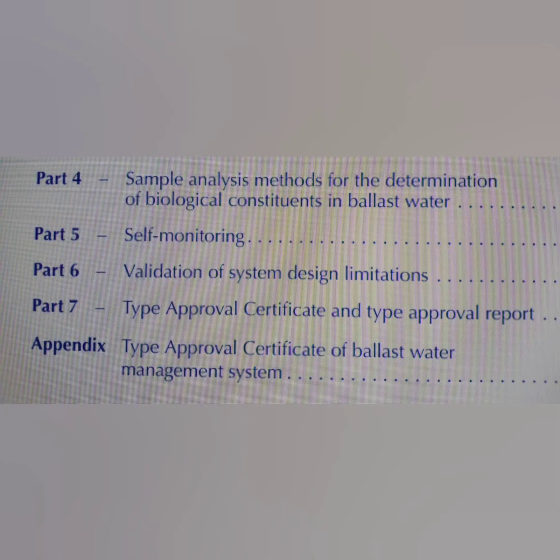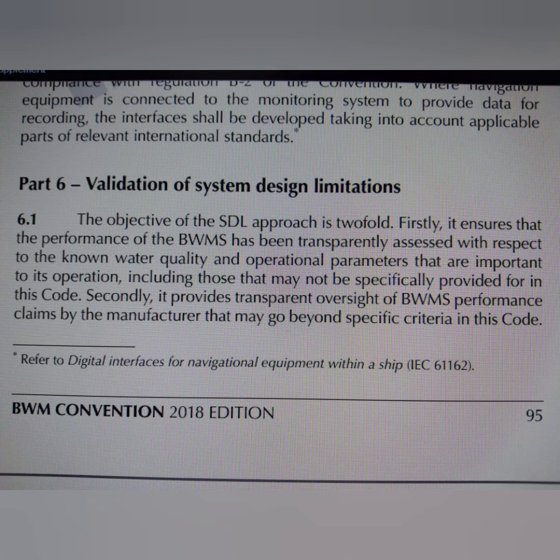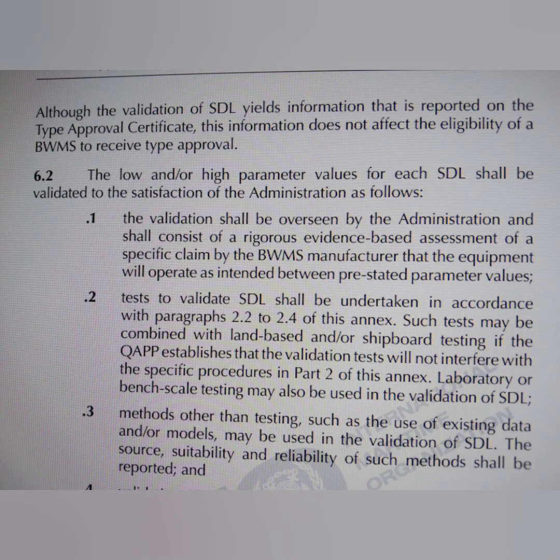Part 6 is about validation of system design limitations. The objective of the system design limitation approach is twofold: first, it ensures the performance of the ballast water management system has been transparently assessed with respect to known water quality and operational parameters important to its operation, including those not specifically provided in this code. Secondly, it provides transparent oversight of the ballast water management system performance claims by manufacturers that may go beyond specific criteria in this code. Validation of system design limitation yields information reported on the type approval certificate but does not affect the eligibility of the system to receive type approval.